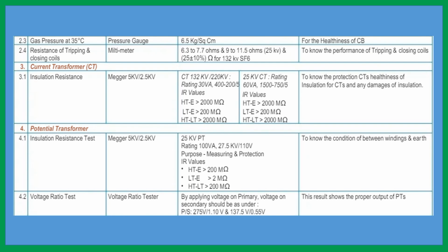Then voltage ratio test. By applying voltage on primary, voltage on secondary should be measured as under. Then check the ratio. But you cannot apply 25 kV. So how much will you apply? 275 volt by 1.10 volt, or 137.5 by 0.55 volt. You can check it. We know the ratio, it is 27.5 by 110. So in that ratio, if you reduce the voltage in the primary, you can find out the ratio. If it is permitting this voltage, then it is okay.